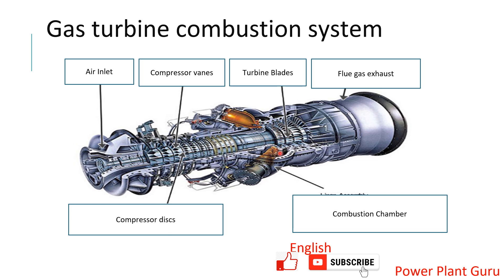You cannot directly measure the temperature inside the combustion zone because of the high temperature environment and the rotating parts. So what you do is measure the temperature at the exhaust of the turbine. There you have many thermocouples, and those give you an idea of what the temperature is at the combustion stage.